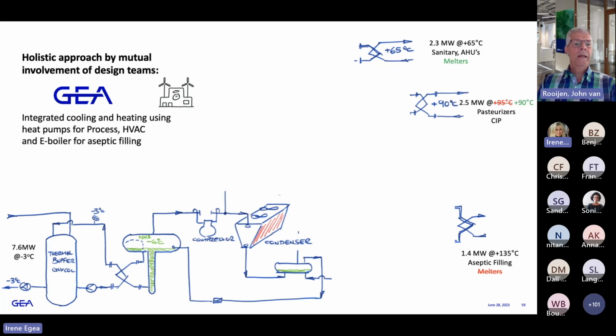We focused on integrated cooling and heating solutions with heat pumps for the process part, HVAC, and e-boilers for the aseptic filling. What you see now on the bottom right part is that the melters are no longer on steam. They have moved to the upper part of hot water at 65 degrees, and we minimized the hot water temperature of 95 degrees to 90 degrees, being able at that moment to generate also that heat with heat pumps. Please forward one animation.